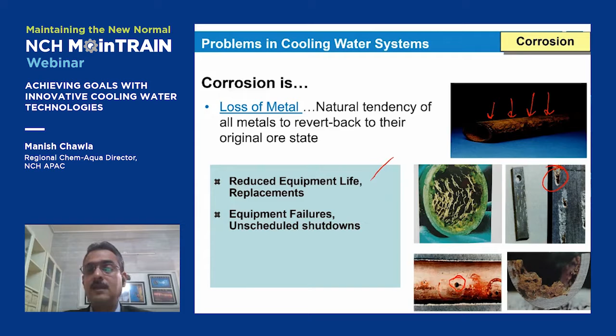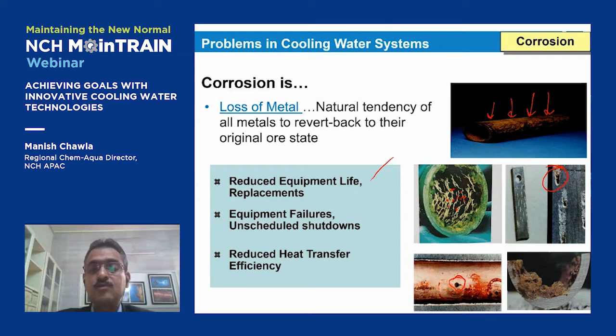In the end, all this means reduced equipment life—we might have to replace equipment much before its design life. There might be sudden failures, sudden leakages, and we might have to take unscheduled shutdowns, causing production downtime. All this iron oxide coming from corrosion will go and settle elsewhere, and this also has lower thermal conductivity, reducing heat transfer.